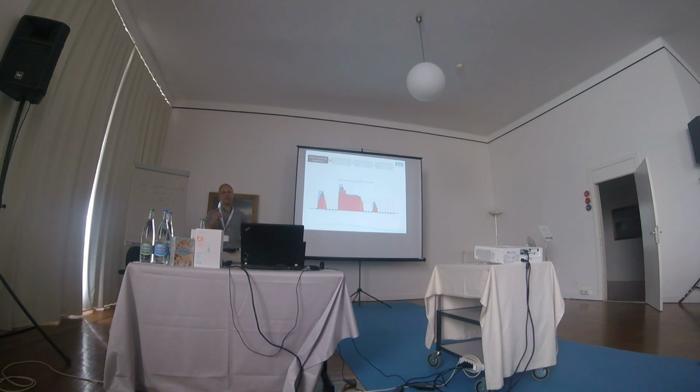Frequency response means how fast they respond to a change in flow. And you see that sometimes they are very, very slow. So maybe you open the faucet, and then it takes a while before the flow rate in the display starts going up, and then when you stop, the other way around, it takes a while before it stops. So they distort the flow traces. Is this important? Well, when we are talking about identifying flow shapes, it can be very important.